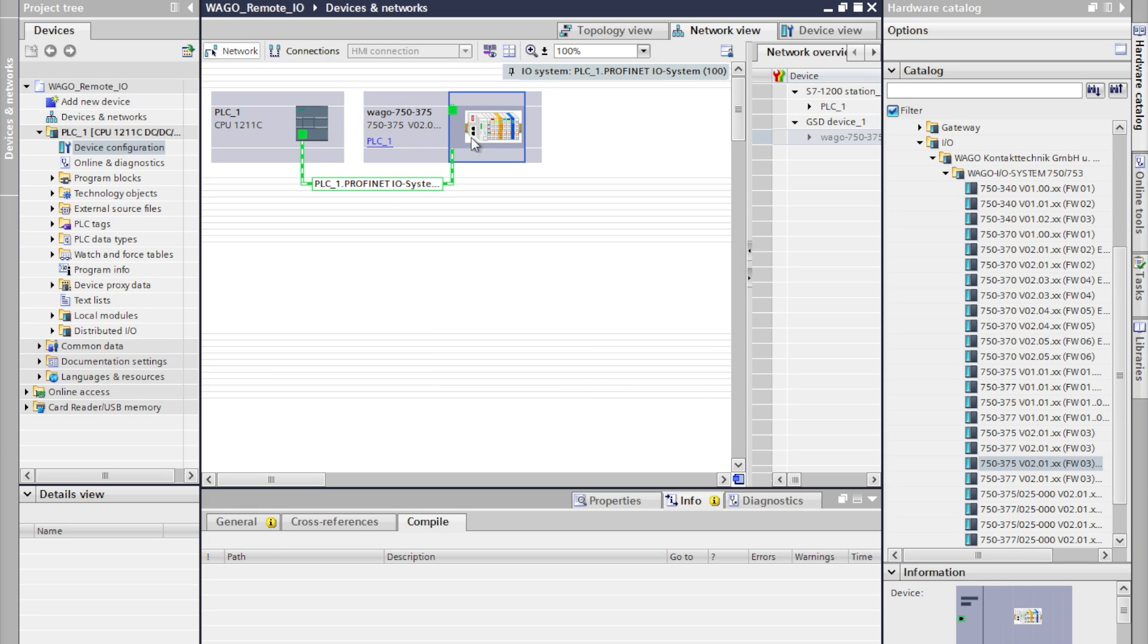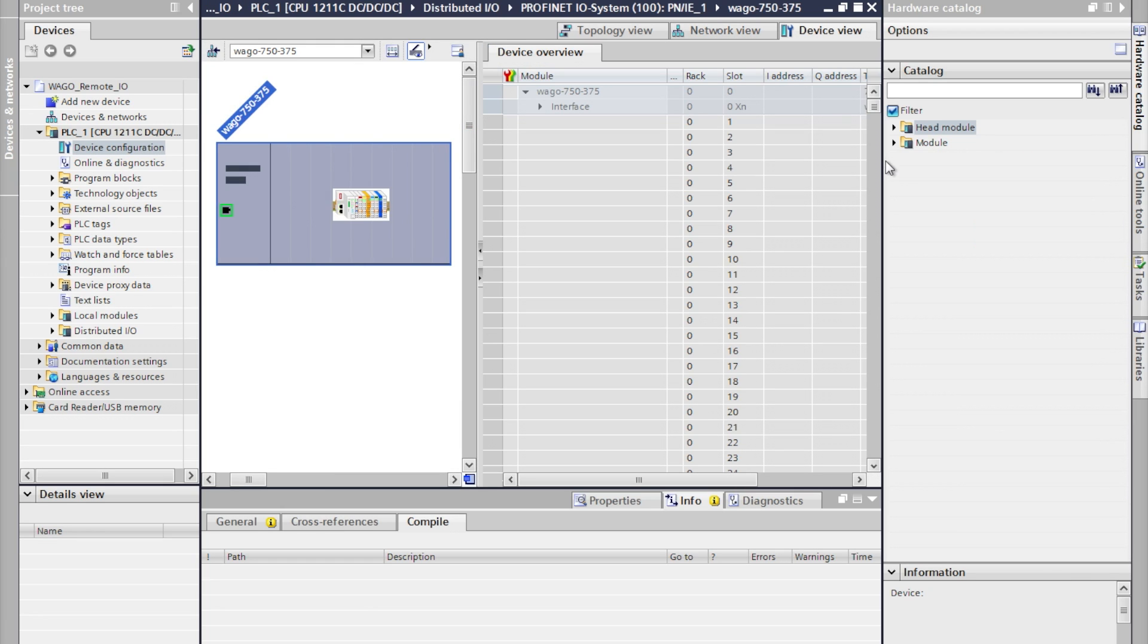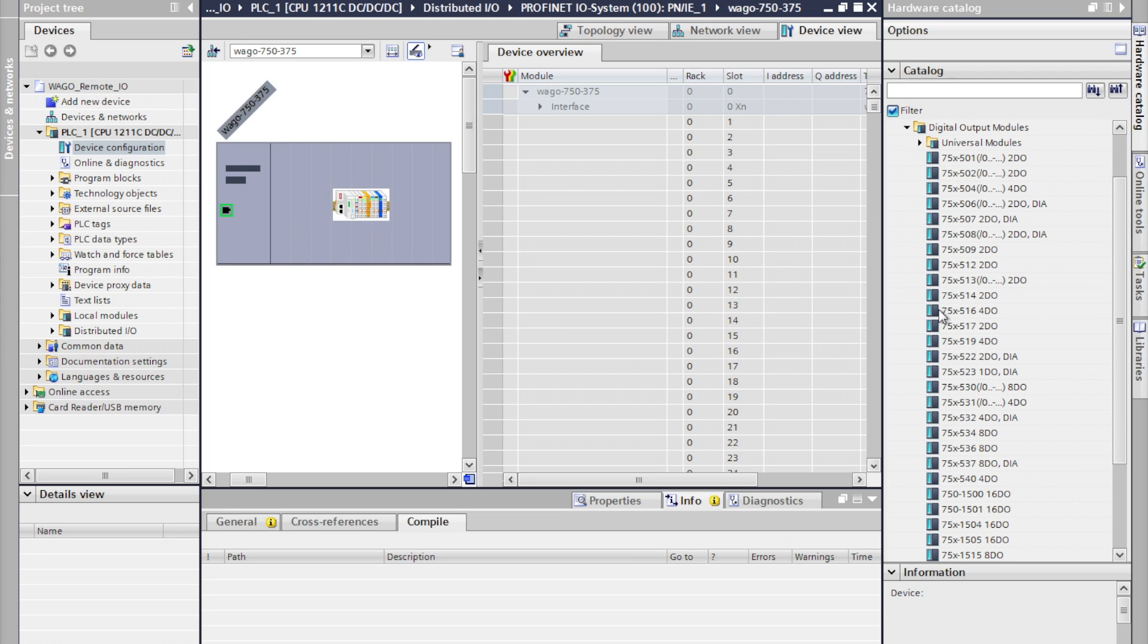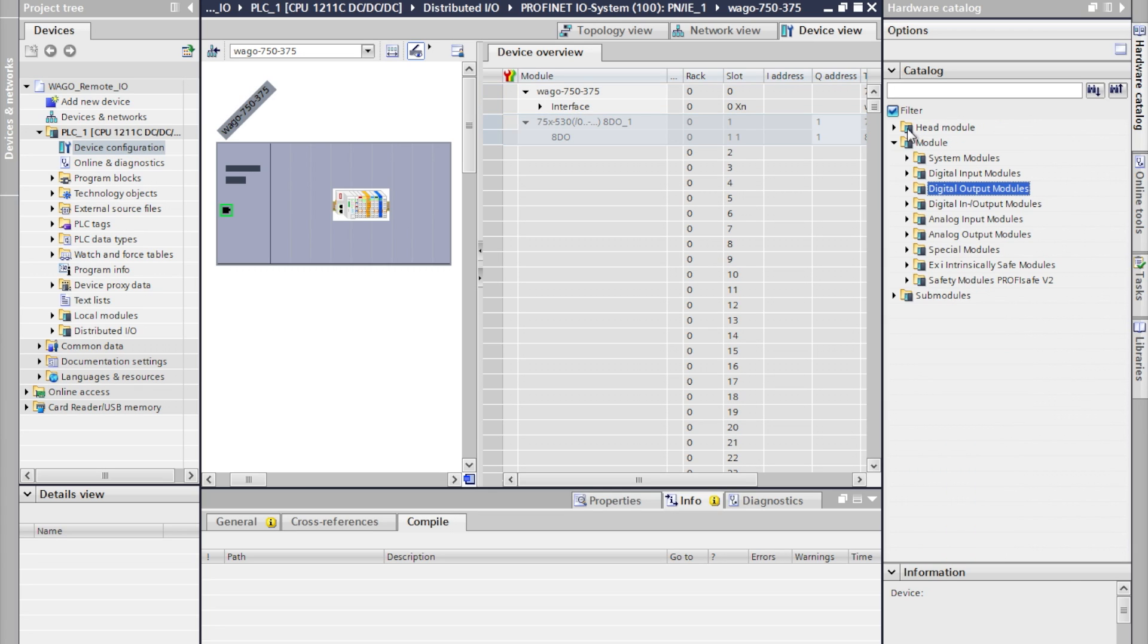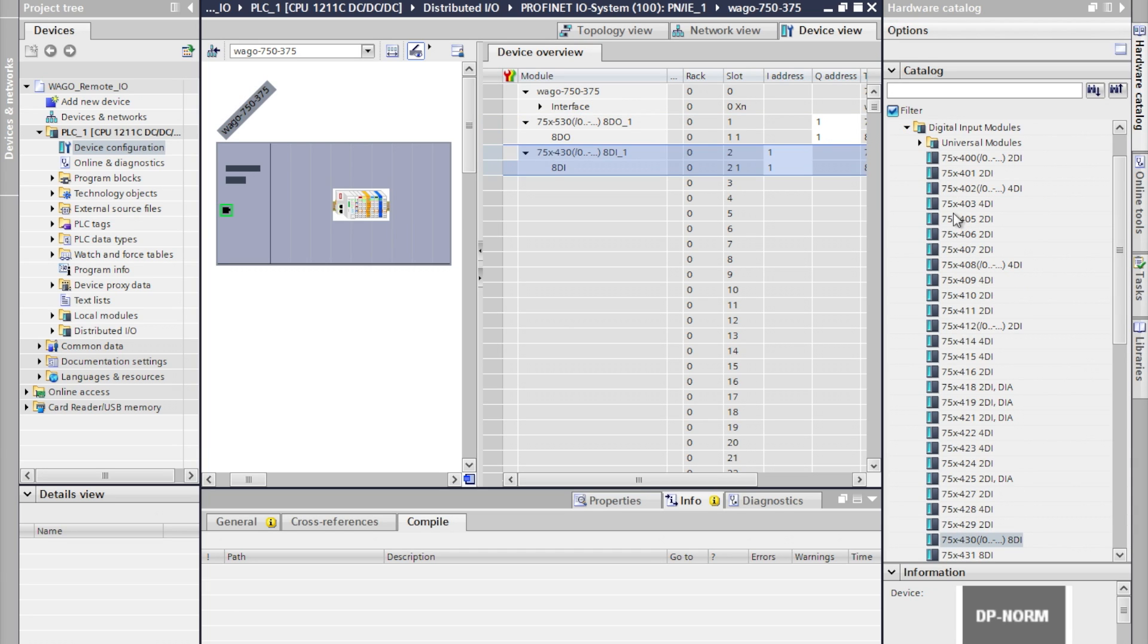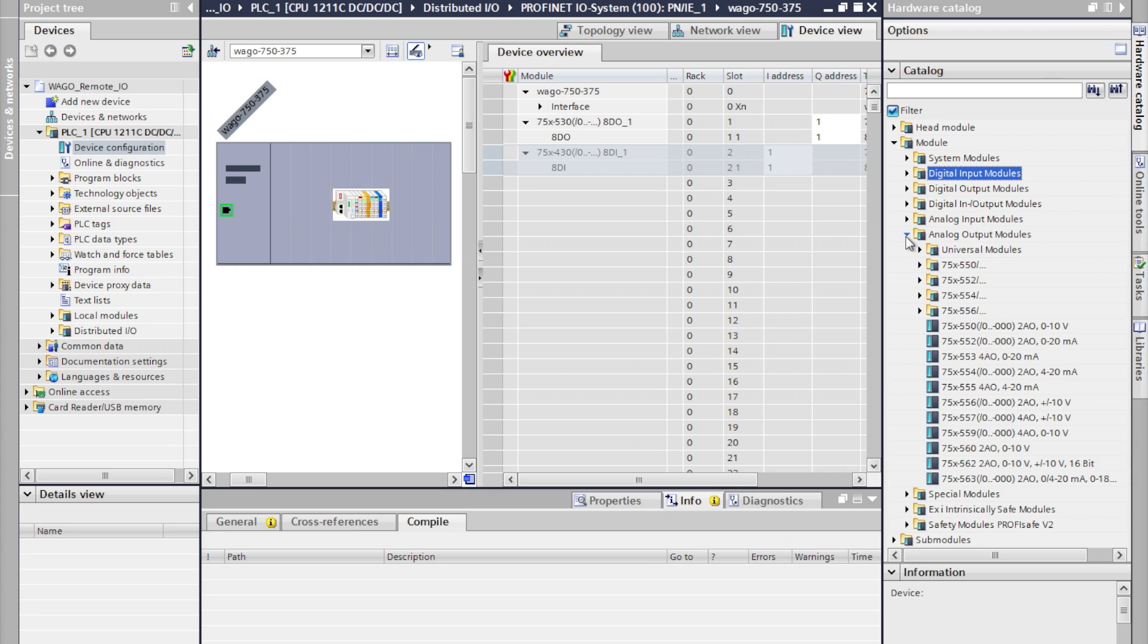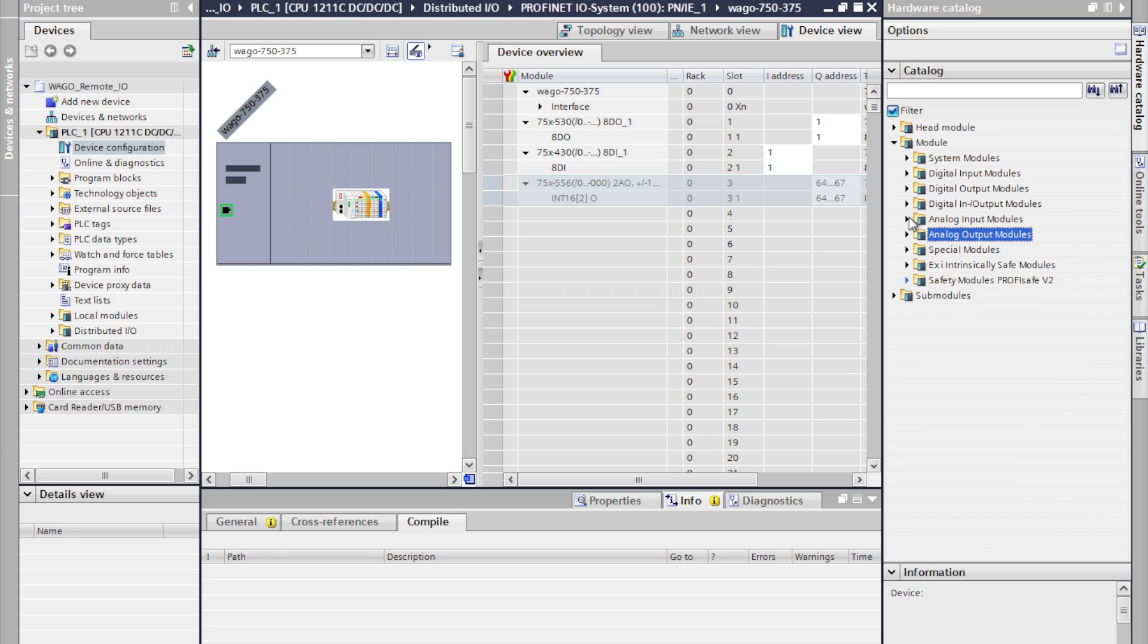By double clicking on the coupler it will take us back into the hardware catalog where we can start to add the modules which will be on our PROFINET coupler. It's important that these are added in the proper order. Unlike some other systems PROFINET is sensitive to the way that these are added so we'll need to make sure that we add them all in the right order as they appear on the back plane.